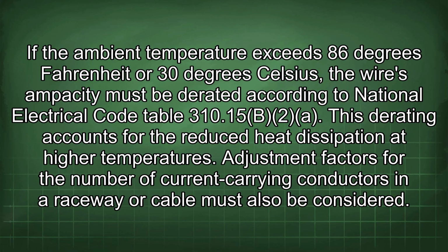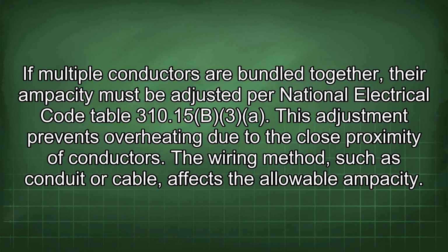National Electrical Code Table 310.15(B)(2). This derating accounts for the reduced heat dissipation at higher temperatures. Adjustment factors for the number of current carrying conductors in a raceway or cable must also be considered. If multiple conductors are bundled together, their ampacity must be adjusted per National Electrical Code Table 310.15(B)(3). This adjustment prevents overheating due to the close proximity of conductors.